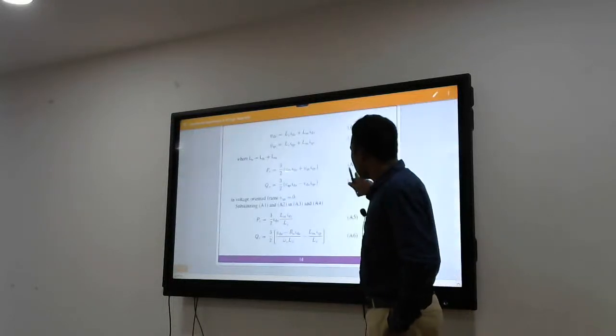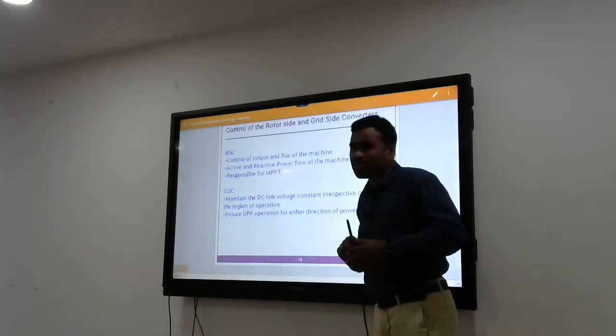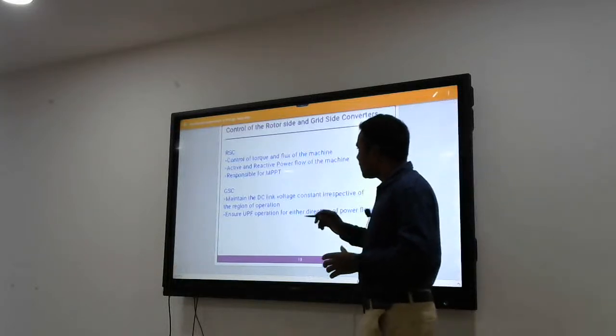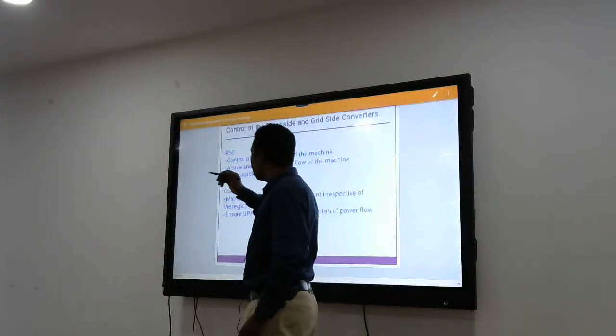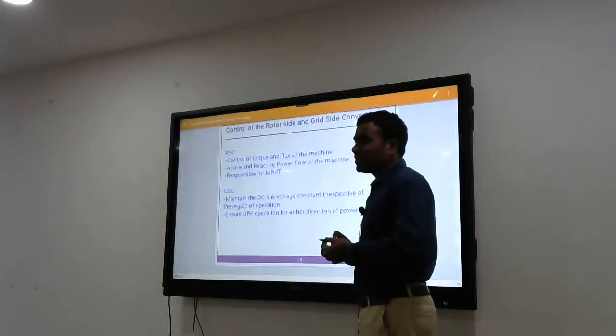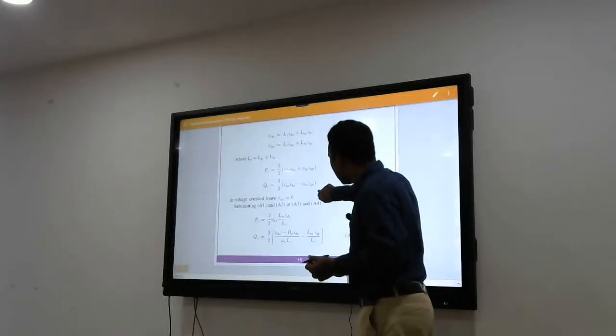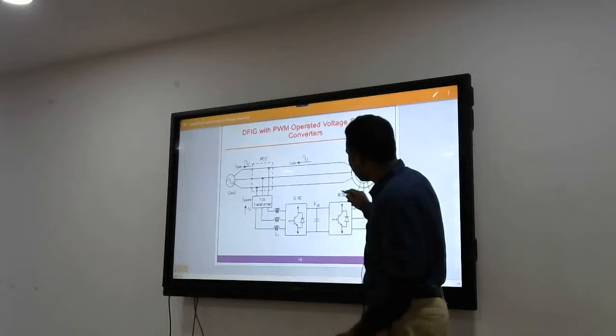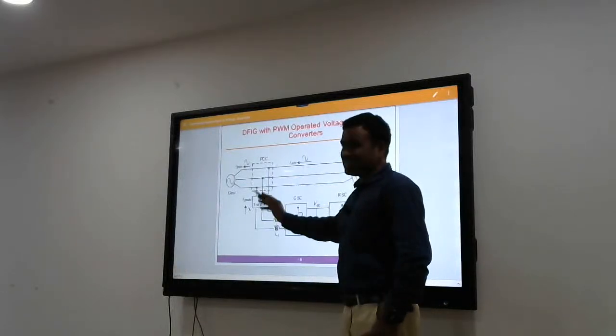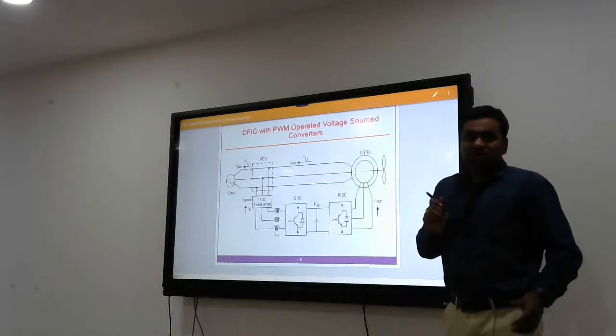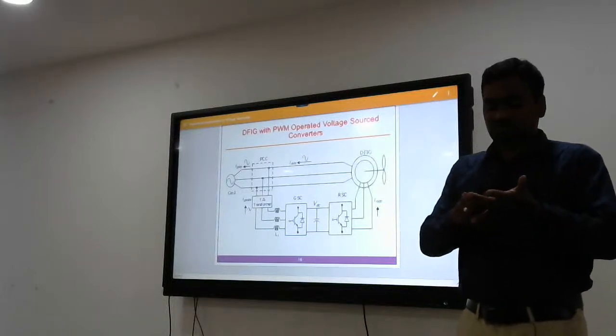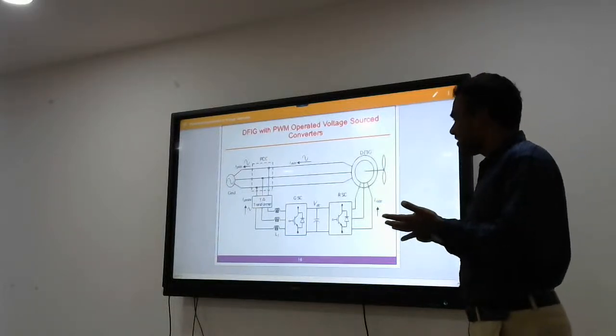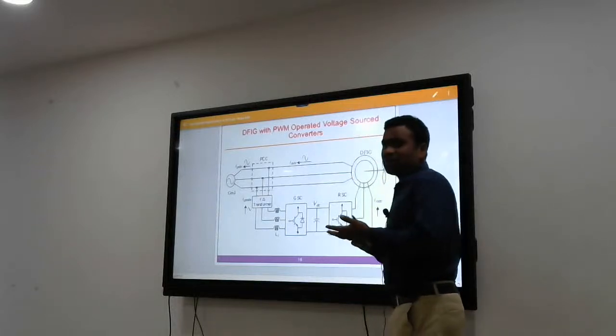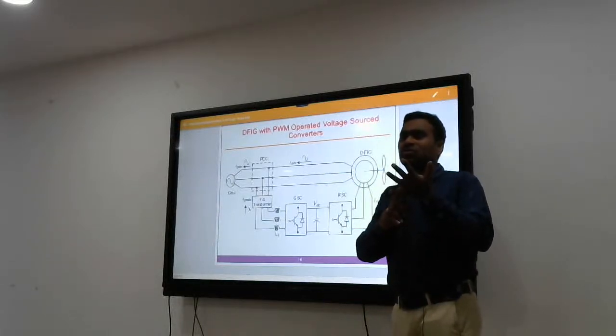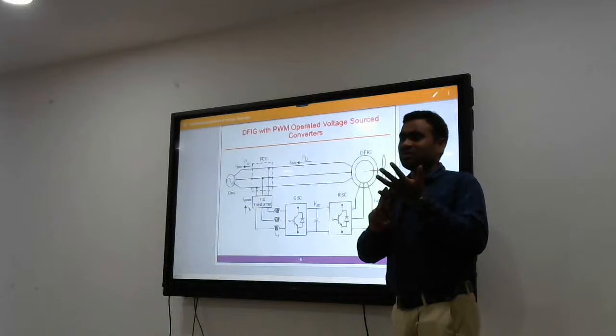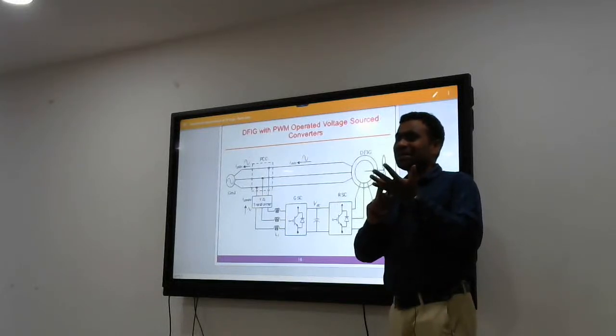Okay, now there are two converters. The first one is RSC, the rotor side converter. With the help of this rotor side converter, maybe I have to go back again. This is RSC, rotor side converter. This is the grid side converter. I told a series of events or a series of equations: for achieving MPPT, you have to change the speed.